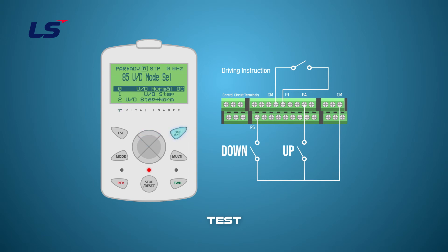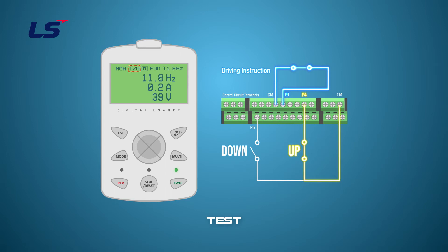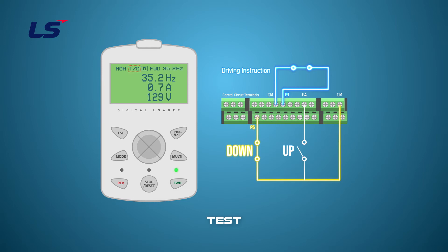Then, the frequency command source display at the top of the monitor mode changes to S. In this state, when the multifunction input programmed as Up is on, S changes to U and the frequency increases while it is on. When the multifunction input programmed as Down is on, S changes to D, and the frequency decreases while it is on.